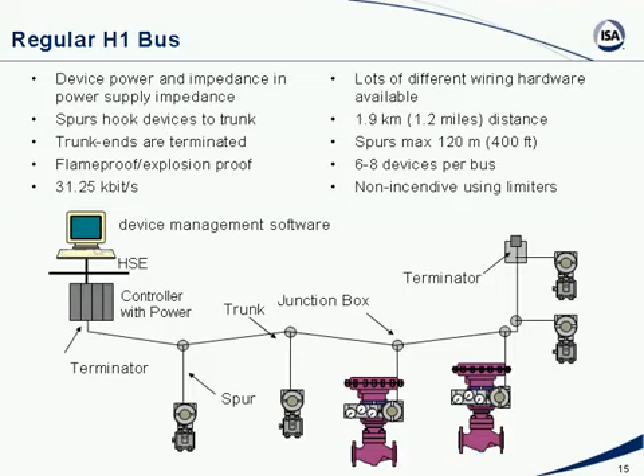Really the purpose of the terminator is not so much to reduce reflections. It is in fact that field bus devices transmit by a current signal, but they receive a voltage signal. So the main function of the terminator is as a shunt, to convert the transmitted current to a voltage that is received by all the other devices. Obviously, this wiring scheme would also be used if you do a flame-proof installation. You would just run the trunk inside conduit or using armored cable.